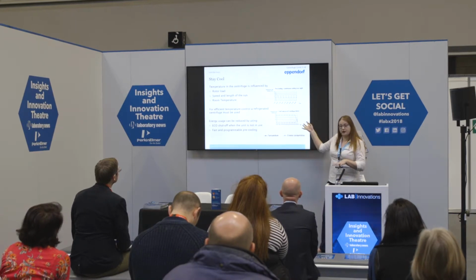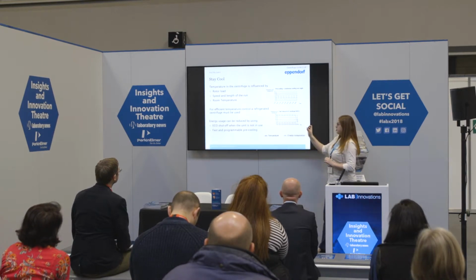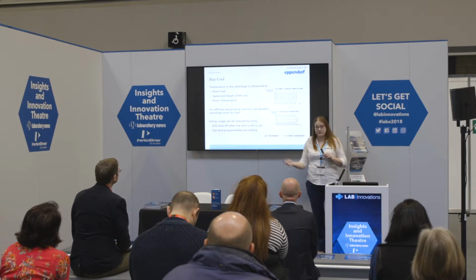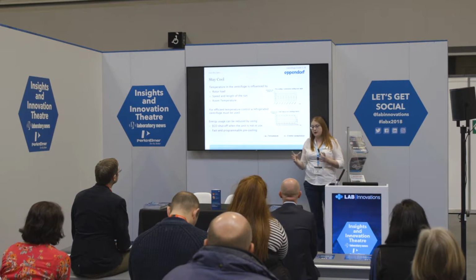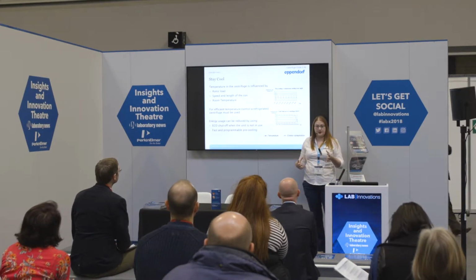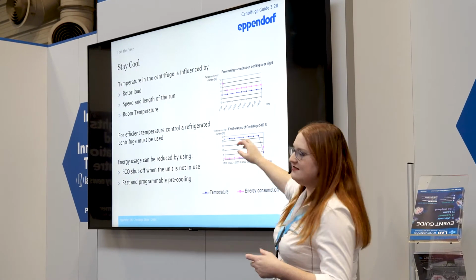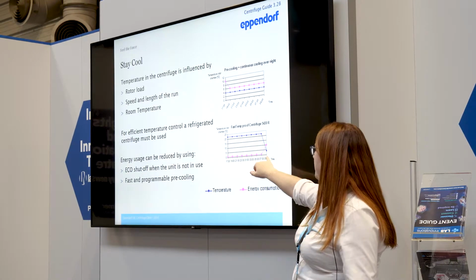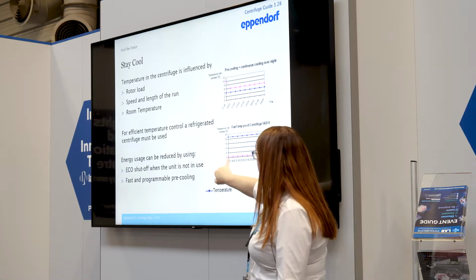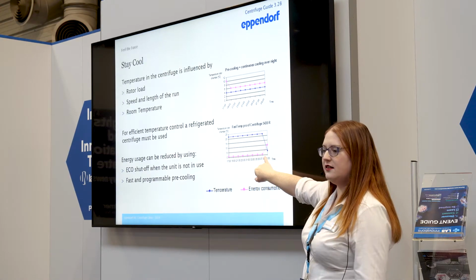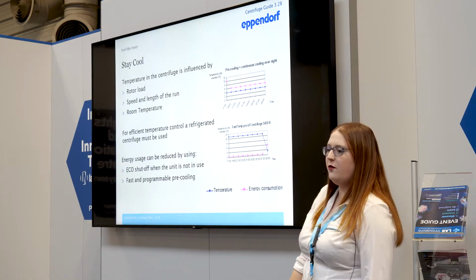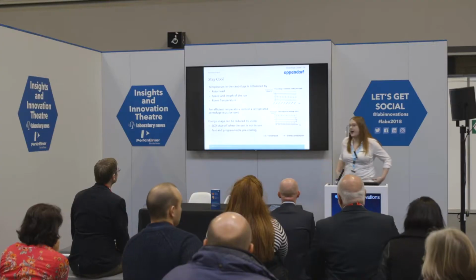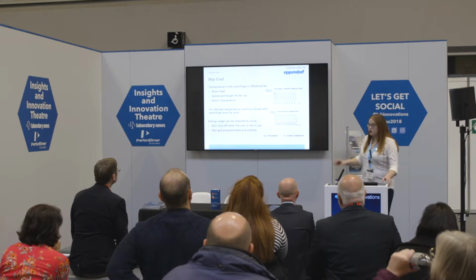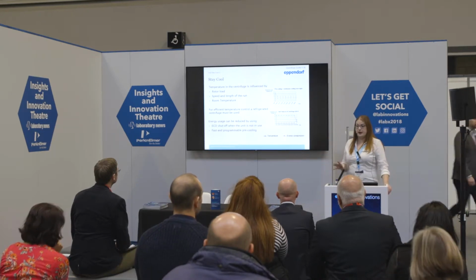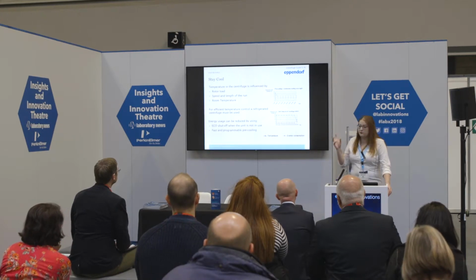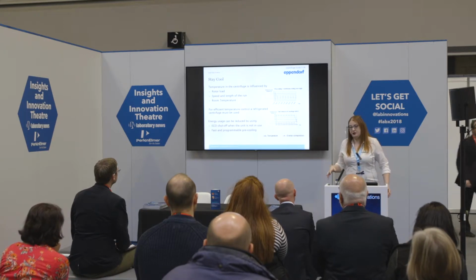The alternative is what we call fast temp. Other manufacturers do have their own versions, but ours is fast temp. Basically what this does is it spins up the centrifuge empty before you use it. It uses the motion of the rotor to help the compressor to cool down the rotor and the chamber faster. Okay? So this means the temperature was really warm all night because it was just at room temperature. But then it comes right down first thing in the morning, ready to be at 4 degrees at 9 o'clock. But in comparison, the energy was really, really low all night because it wasn't doing anything. And then it just peaked a little bit when you actually cooled it down. So in terms of energy usage, which is a big problem with refrigerated centrifuges, using something like fast and programmable pre-cooling is really, really worthwhile. And the other thing that most of them have now is an eco shut-off. So if it's left on for too long, it will turn itself off.